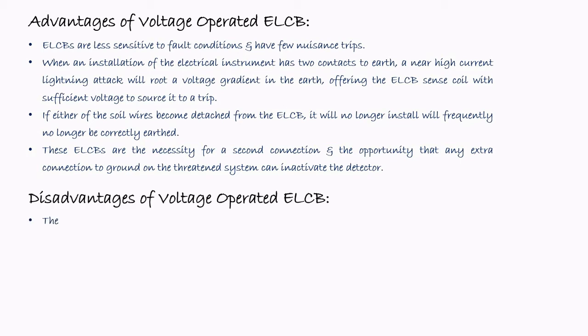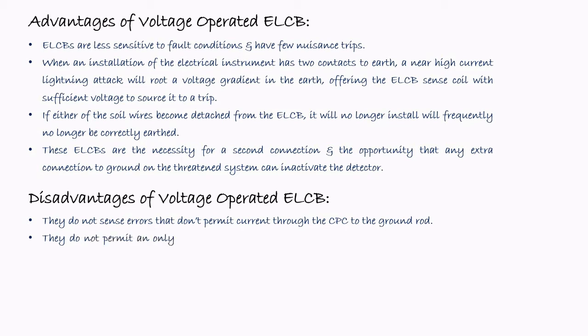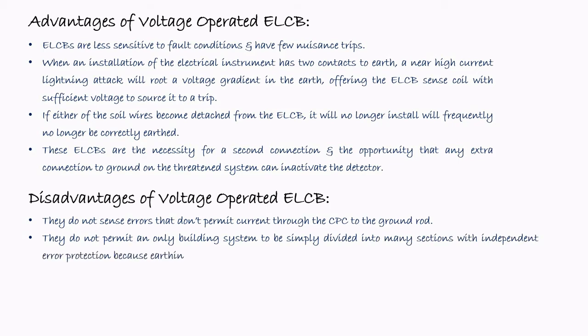Now some disadvantages. They do not sense errors that do not permit current through the CPC to the ground rod. They do not permit an entire building system to be simply divided into many sections with independent error protection, because earthing systems typically use a mutual earth rod. So as we have already discussed, it will protect only the equipment with which this ELCB is connected.